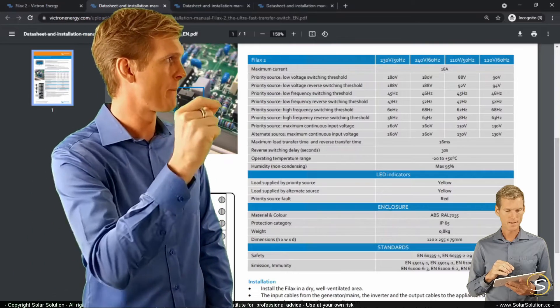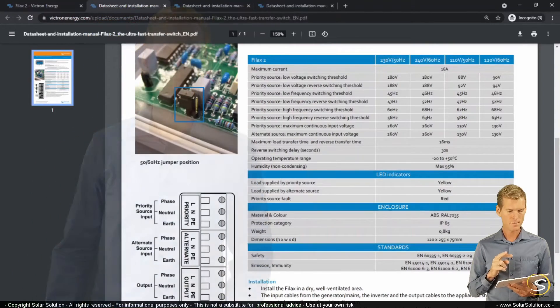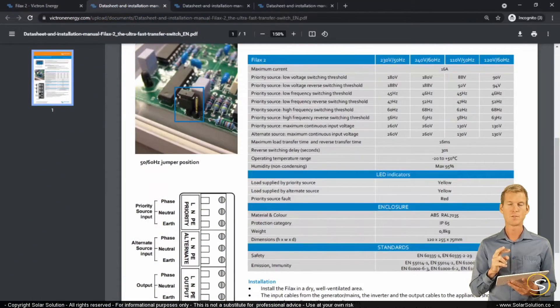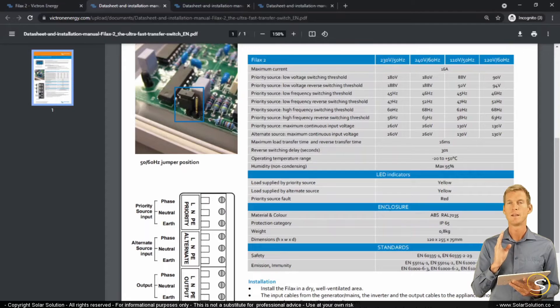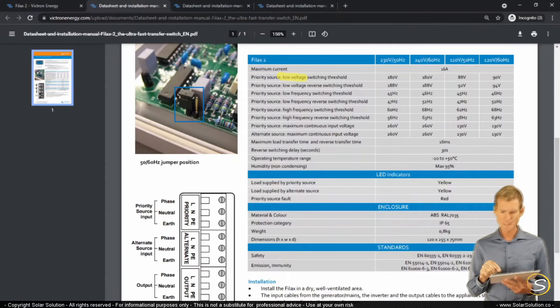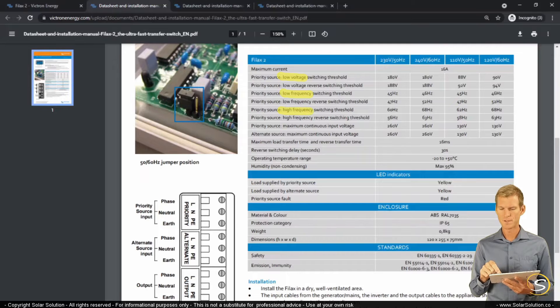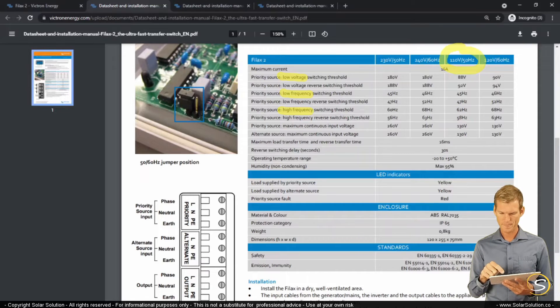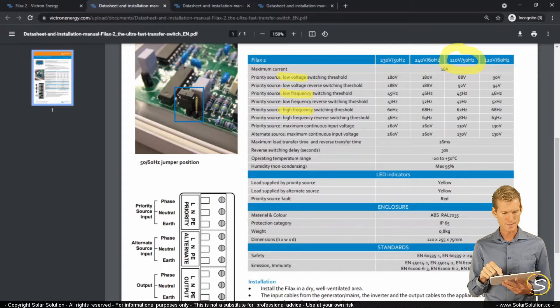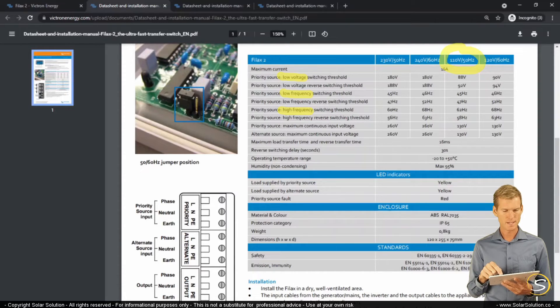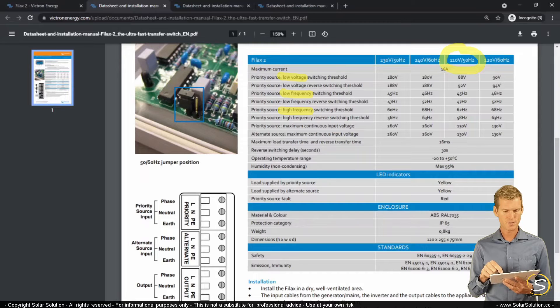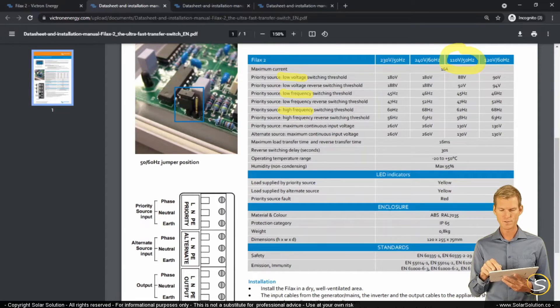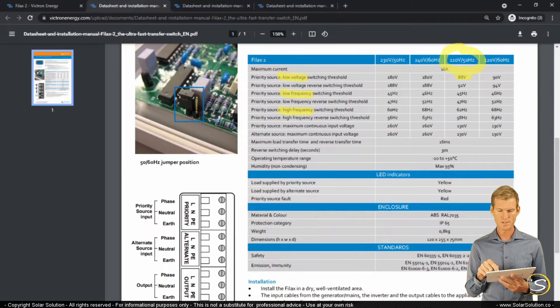And then based on three set parameters, it will decide whether it will switch between the grid or your generator. So let's assume you're running a 110 volt, 50 hertz system. So look in this column. And you can see here that it will switch from your grid towards your generator if it hits the low voltage switching threshold. And if it's lower than, if it's equal or lower than 88 volts, it should switch towards your generator.